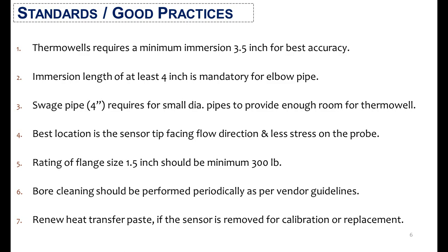Thermowells require a minimum immersion of 3.5 inch for best accuracy. Secondly, an immersion length of at least 4 inch is mandatory for elbow pipe. Also, a swage pipe of 4 inch size is required for small dia pipes to provide enough room for the thermowell.